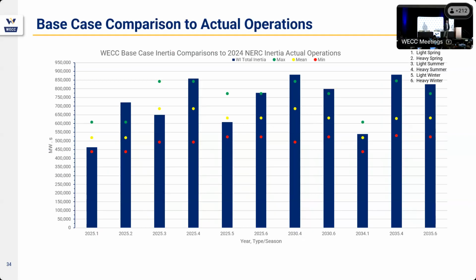The math doesn't math. So if I was going to state a risk, and it might be on our risk register someday, it's the model accuracy due to IBR integration is not matching what we think is actually going to be built in the system. This is really important. It means when you're talking about an IBR, it's not just inertia. It's short circuit ratios, it's a whole bunch of other electrical engineering attributes that synchronous machines have - a much different attribute than an IBR. And our transmission planning cases are not matching what we're seeing in our historical data.